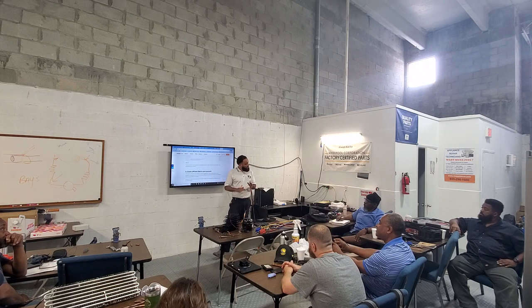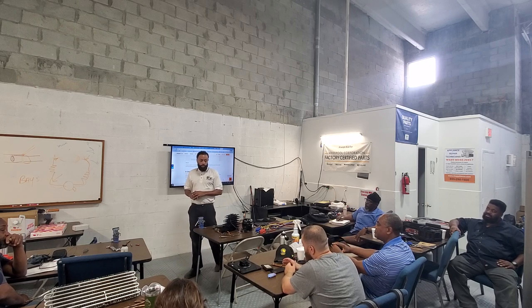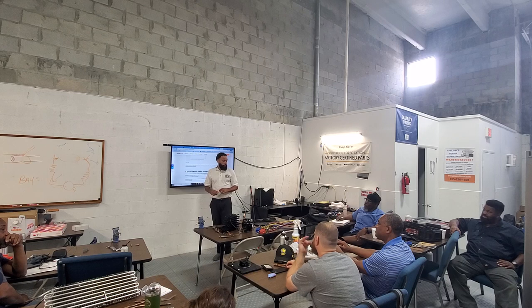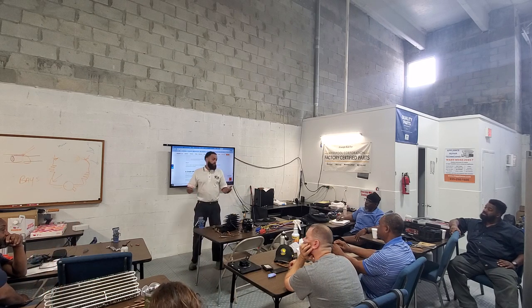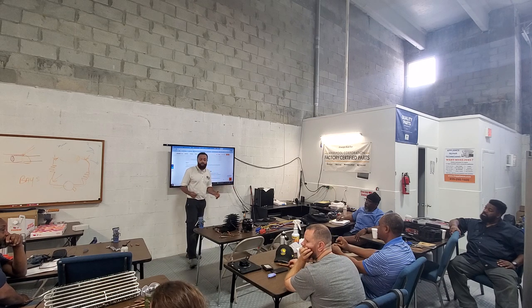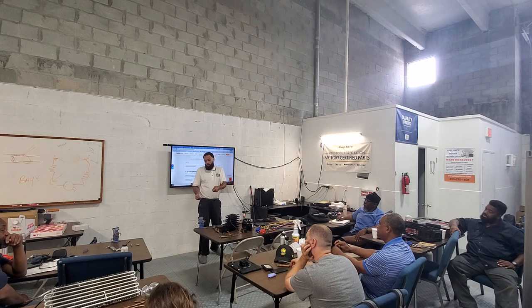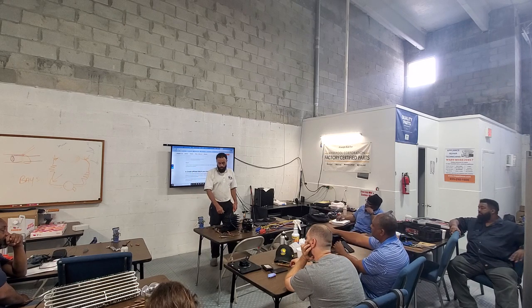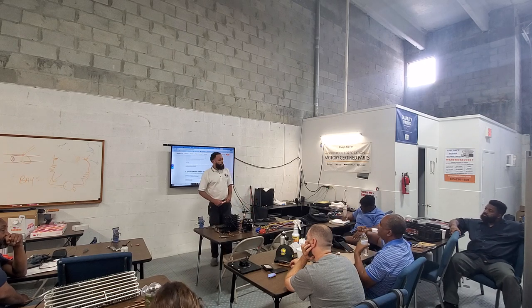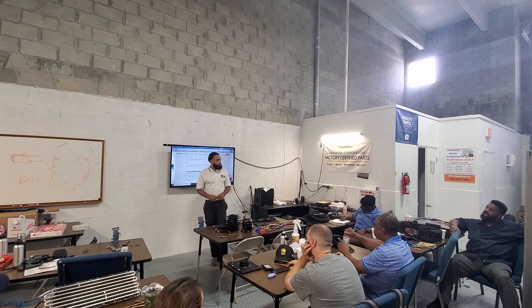Never exceed the low side, and you'll be okay. Never go over the low. Why would you exceed it? You might damage the evaporator. I don't know why they even include the hot side. I guess if you isolate the system, or you want to put the condenser coil on the PSI, that's the most you could do. It's a different metal than the evaporator. But don't exceed the low side, you'll be okay. Oh, I see what you're saying.